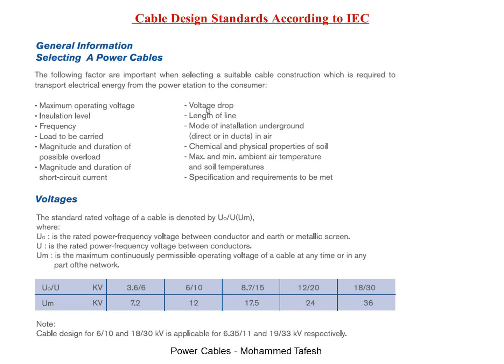Also important are the magnitude and duration of possible overload, magnitude and duration of short circuit current, voltage drop, length of line, mode of installation — underground direct, in ducts, or in air — as well as chemical and physical properties of soil, maximum and minimum ambient air and soil temperatures, and other specifications and requirements to be met.